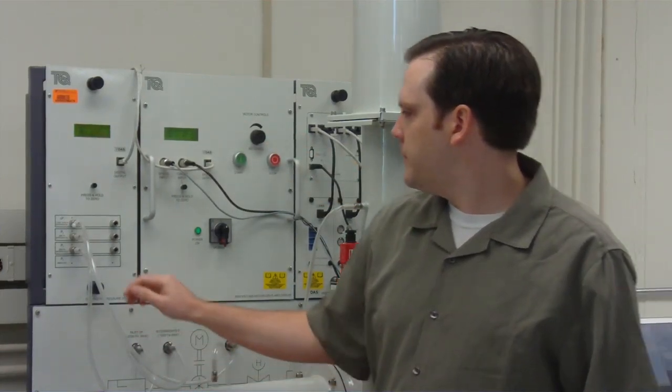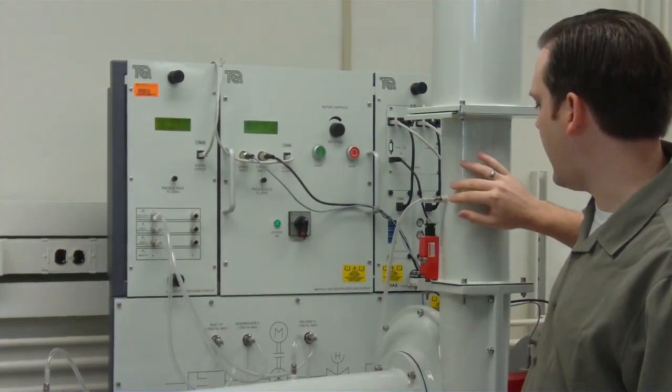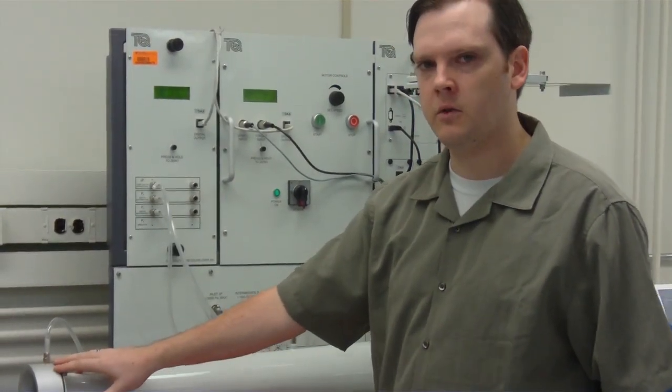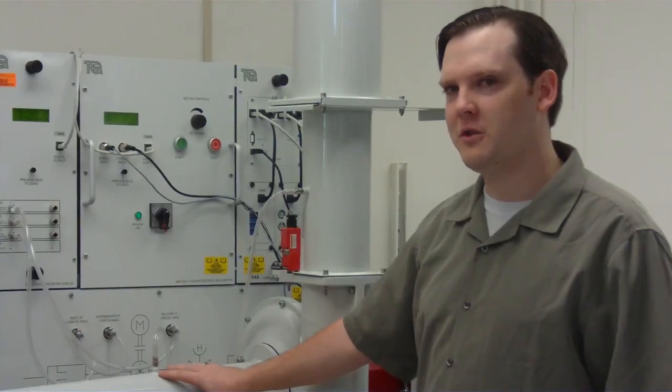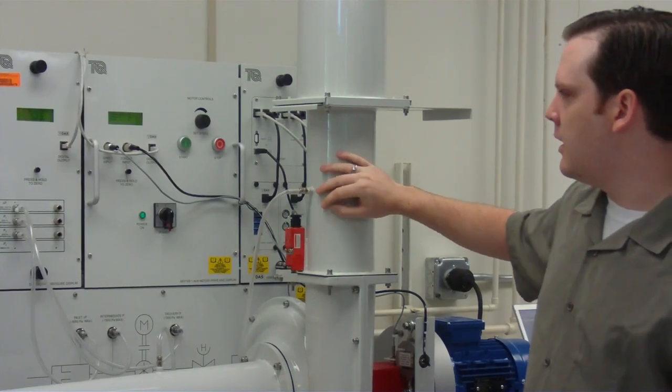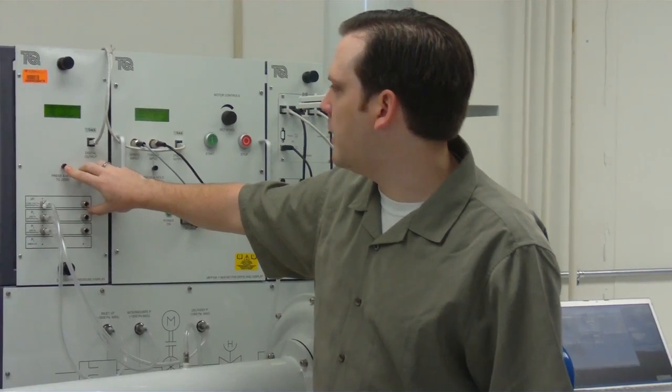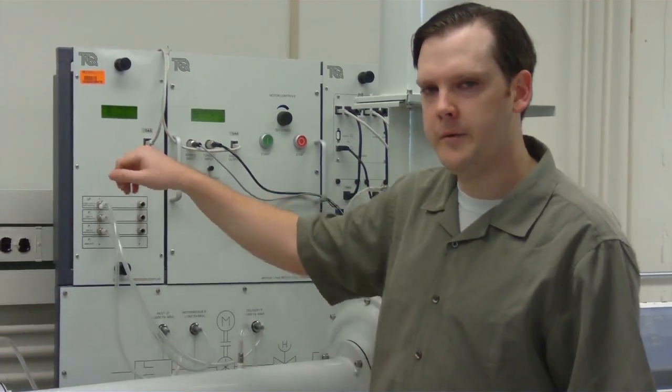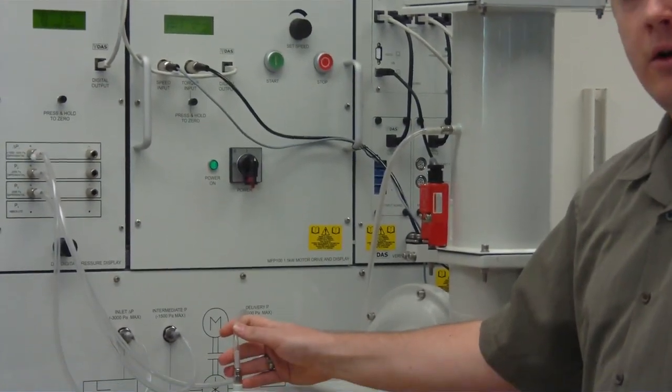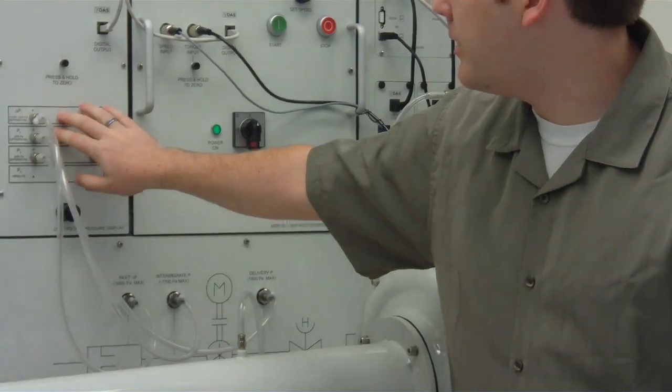The pressure gauges are on this panel here. Each of them connects to a pressure tap on the unit. P1 is here at the nozzle, P2 just before the impeller, and P3 just after the impeller. They all read out here, and you can zero those values by pressing and holding this button while the unit is turned off. Before you begin, check to make sure that all of these lines run to the correct pressure taps, and there are no kinks.